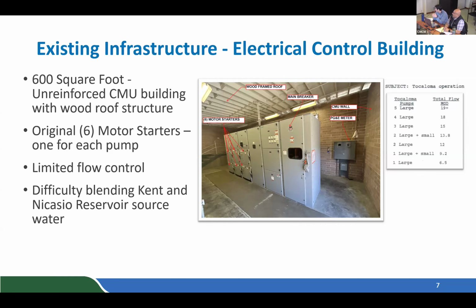So I actually have a small chart here to the right, which is in general what the pumps are capable of. So if you want 12 million gallons of flow rate per day, you turn on 2 pumps. But let's say you wanted 12.5 million gallons to match supply. You can't actually achieve that. You have to jump up to 13.8 by turning on that one small 200 horsepower. And as you go higher up in the flow range, you actually lose control. You get less and less control. And you could actually see that it jumps from 13.8 to 15, then 18.